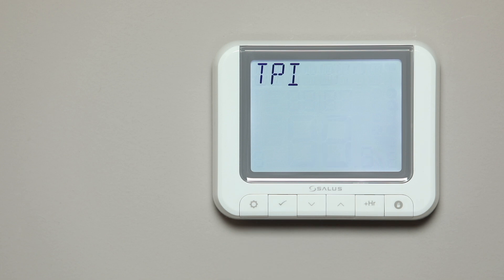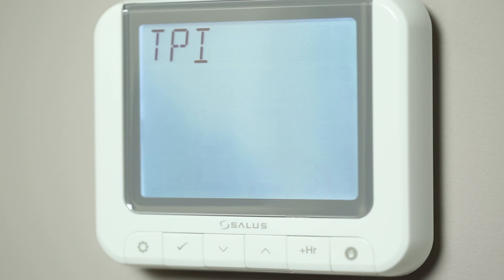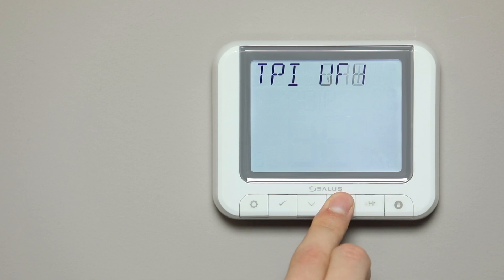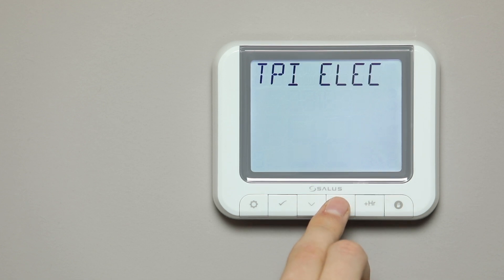The word TPI — time proportional integral — will now appear. Press Tick to enter the menu. Press the Arrow button to select the heating system you are controlling with the RT520 or RT520RF. The options are radiator, underfloor heating, or electric heaters. Press Tick to confirm.